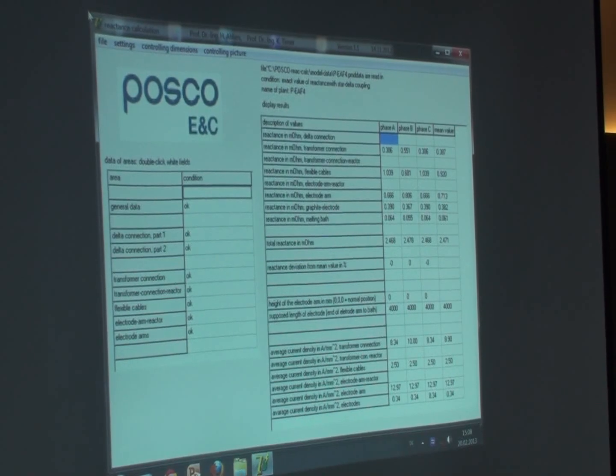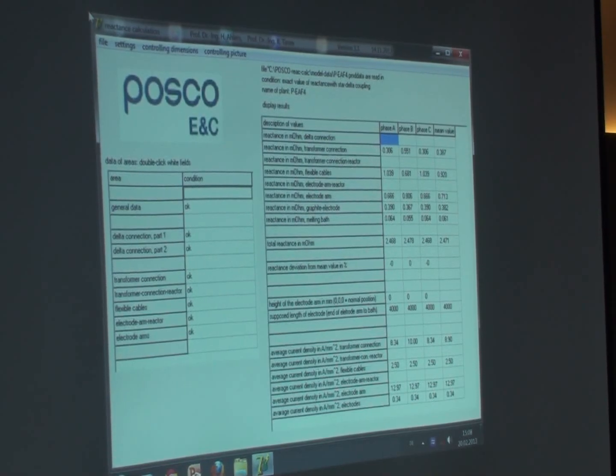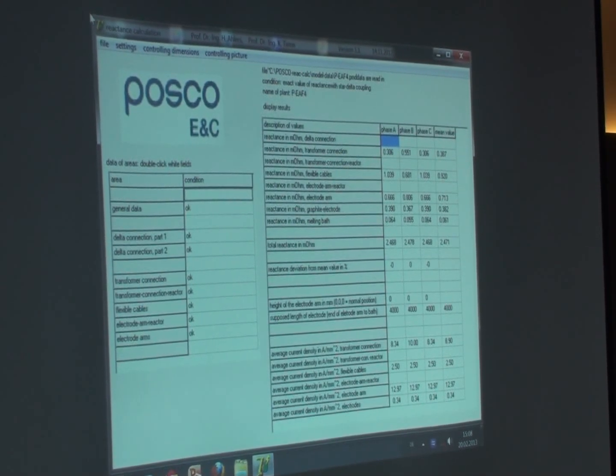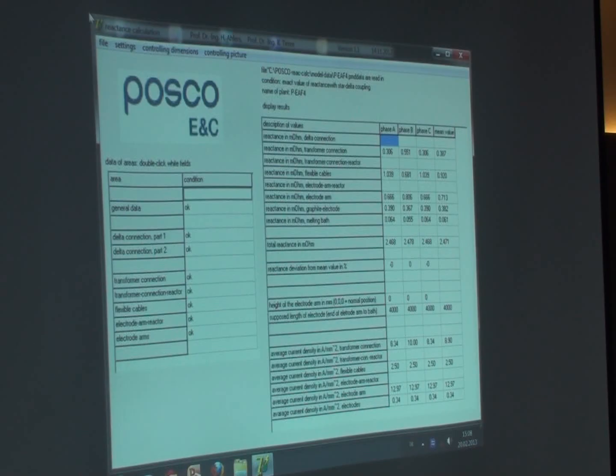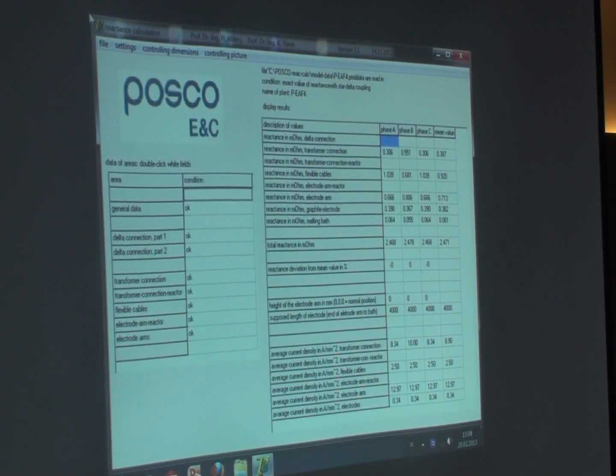These are the loss resistances. This is also, these are about 0.3 to 0.35 milliohms with copper conducting electrodes, yeah, copper conducting arms. This is about 0.5 milliohms with tubes on the electrode holder.